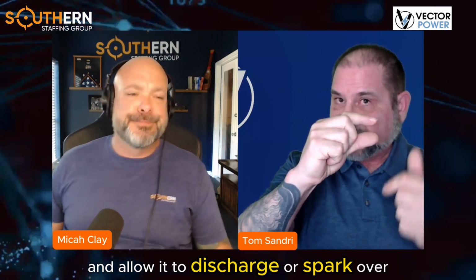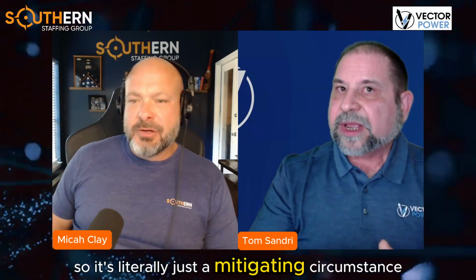You sit there filling it, and it never gets up to the brim or discharges, because you're bleeding out the charge. So by making the dielectric lossier, the intent is we bleed the charge through larger leakage current, but we don't build a charge and allow it to discharge or spark over. It's literally just a mitigating circumstance, trying to get it to where you don't actually reach the point of partial discharge.